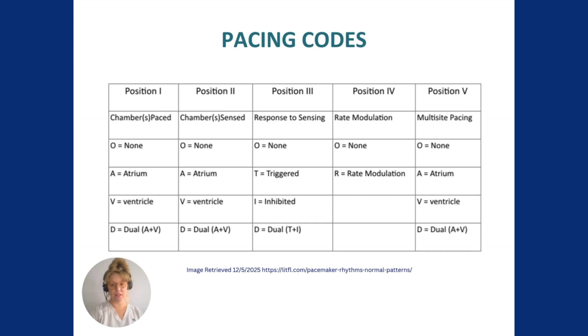So now, in contrast, most temporary transvenous pacemakers are programmed VVI, ventricular demand pacing. So VVI means the ventricle is paced, the ventricle is sensed, and pacing is inhibited if intrinsic ventricular activity is detected. So this one's simple, it's reliable, it's hemodynamically stable, it's appropriate for bradycardia and high-grade AV blocks. That's your VVI. So understanding the mode helps us predict how the device should behave at the bedside.